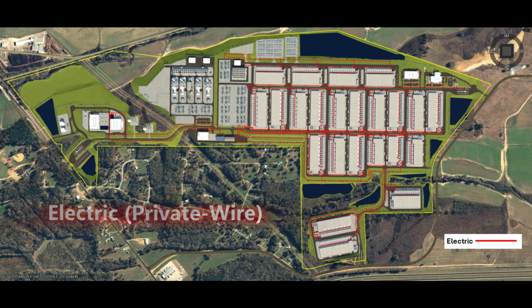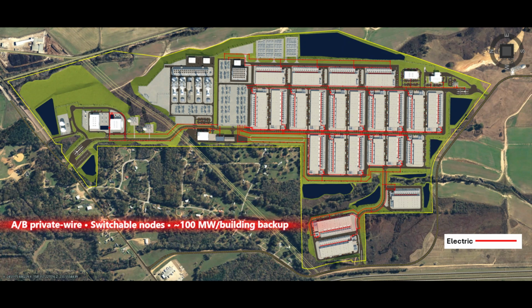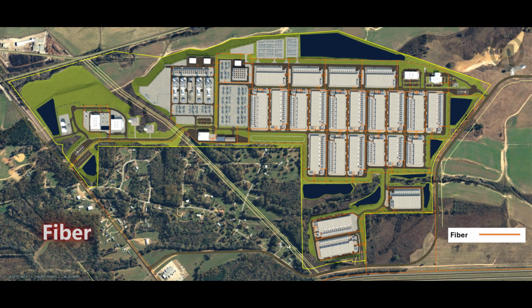Electric private wire. Power is private wire AB, fed from on-site substations to building pads through the grass utility loop. We use switches at nodes for safe isolation and keep feeders out of pavement wherever possible. Recip modules provide approximately 100 megawatts per building of N+1 backup, with fast ramp while the combined cycle plant builds out.